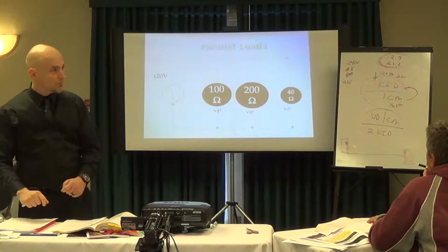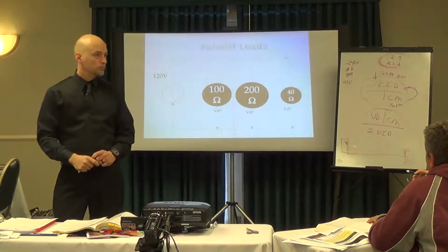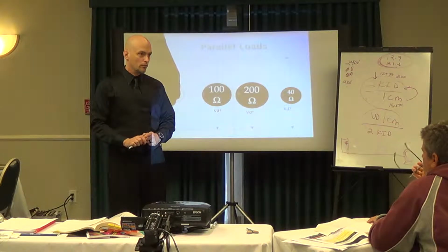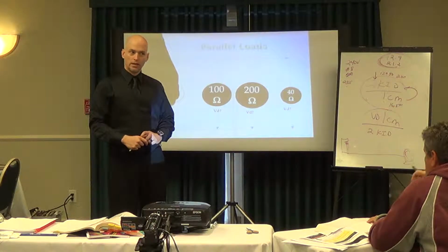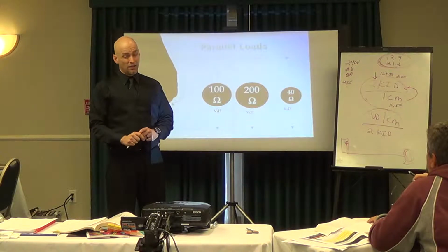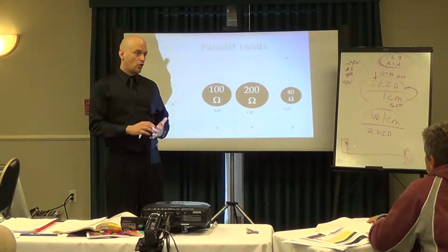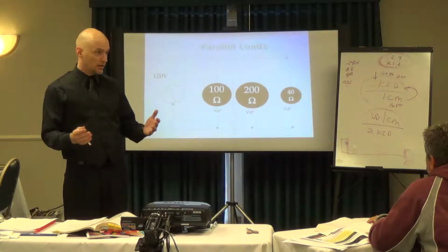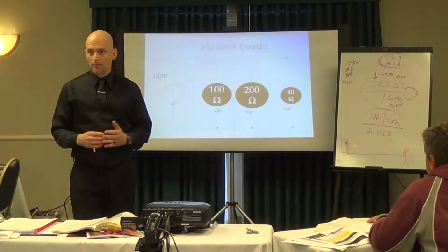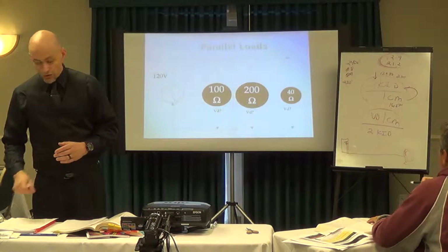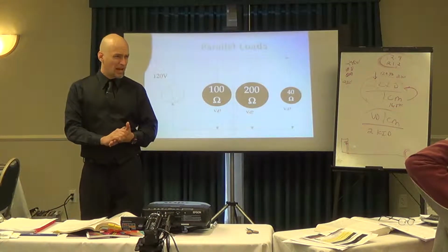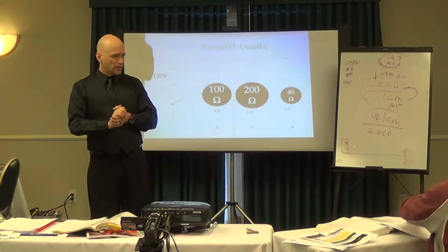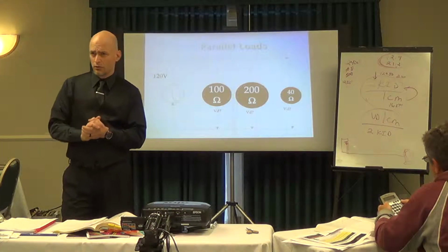So you're saying if they say copper, you know 12.9 goes for K. Yep. And if they say aluminum, it's the other. Yep, that's it. There's no difference. And if they don't say anything at all, it's 12.9. We'll always assume copper. It's like they just give you the wire size and say nothing else, which happens quite a bit. There's actually a code reference for that back in 110. It's 110.5, I think, that tells you to always assume copper unless the statute dictates otherwise.